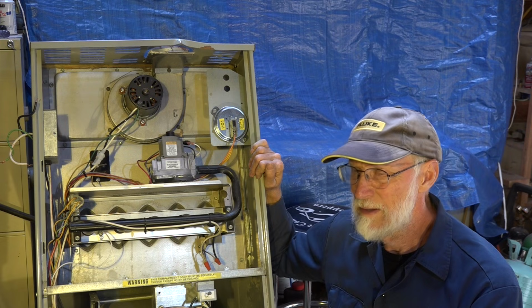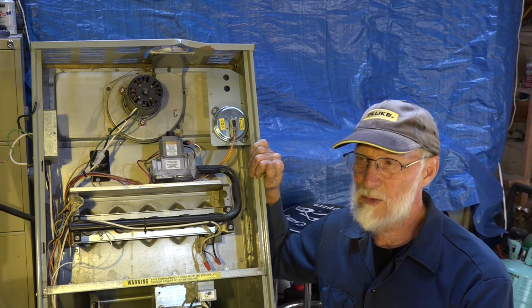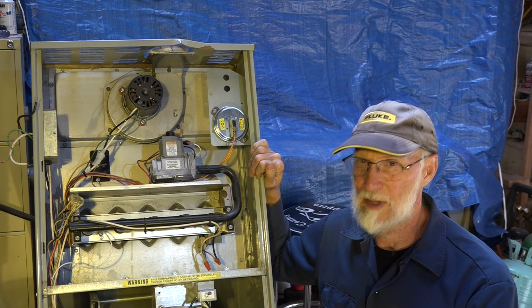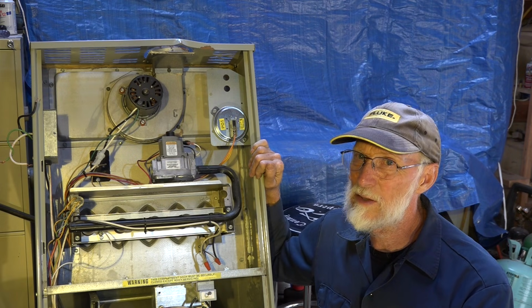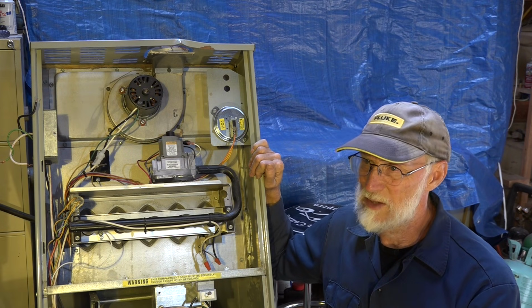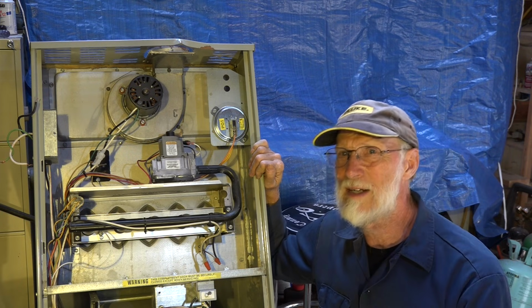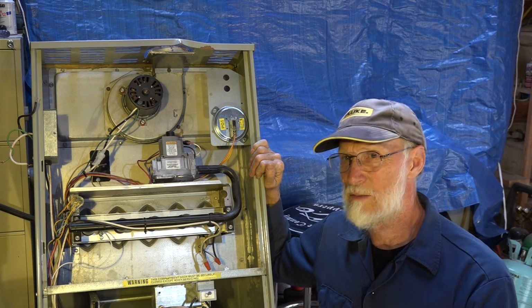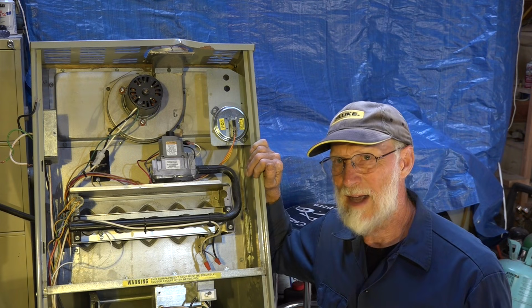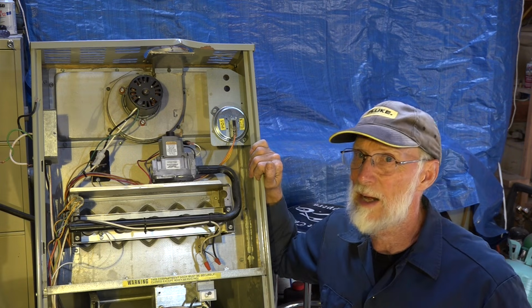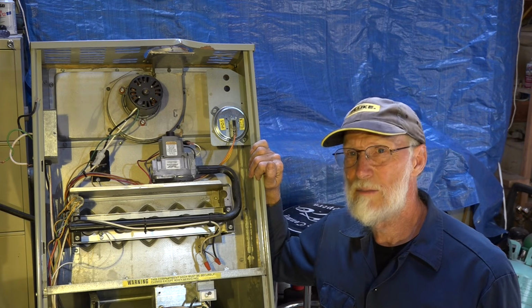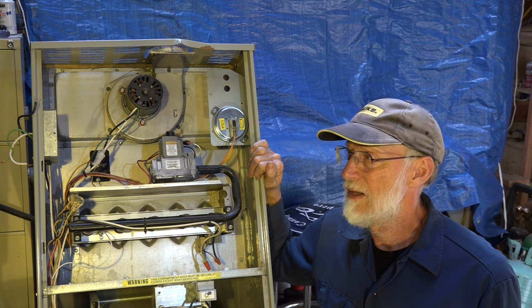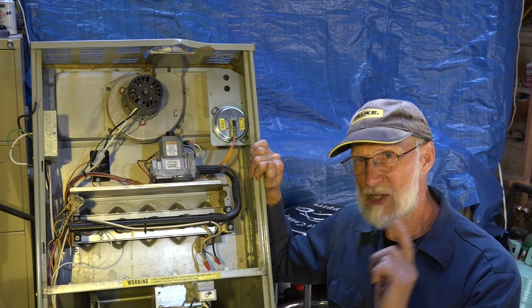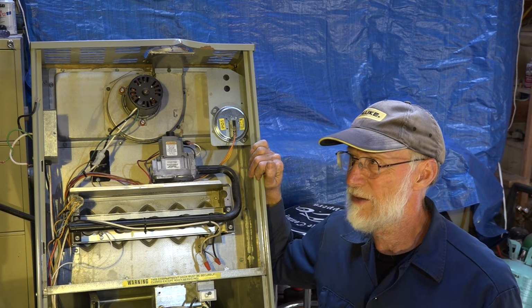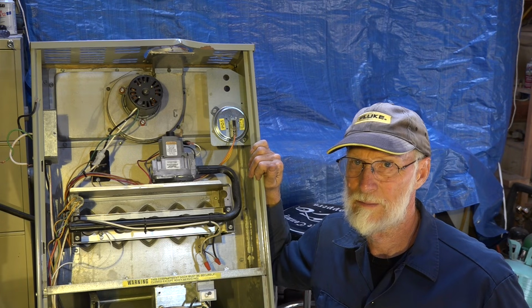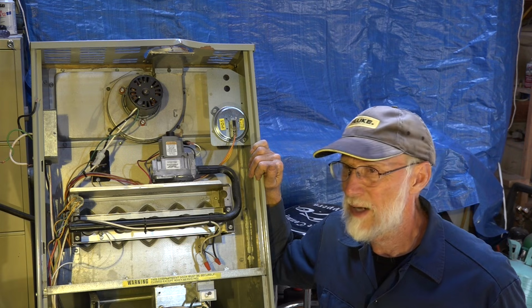Other than that, be very suspicious when someone says you have a cracked heat exchanger, we must replace your furnace. Remember, a lot of these heat exchangers have extended warranties and can be replaced. If you had a cracked heat exchanger and wanted to put extra money with it and buy a newer, more energy efficient furnace, that's a good time to do it. But you need to be sure that heat exchanger is actually cracked before you decide to do that. Remember, CO test, the guy's got to spend some time down there, and you want to see where that crack is. Those things will probably keep you out of trouble.